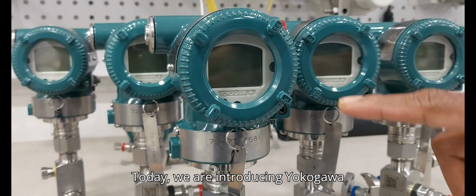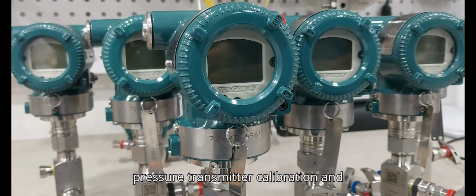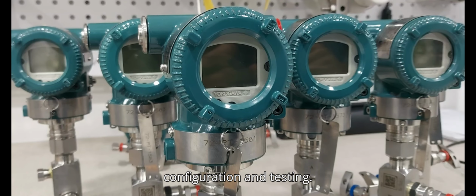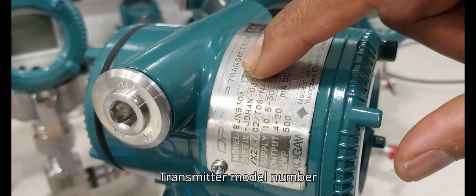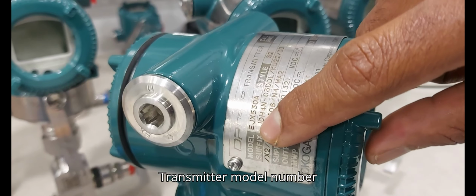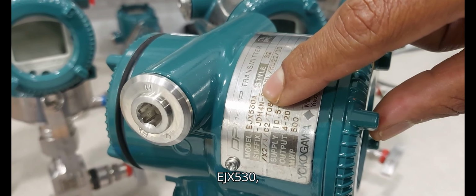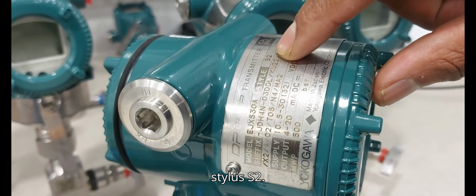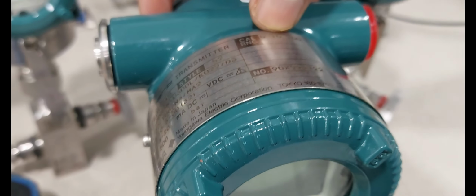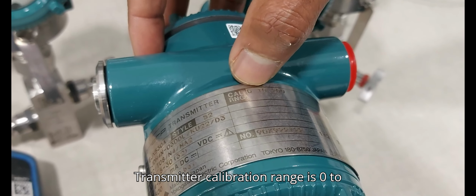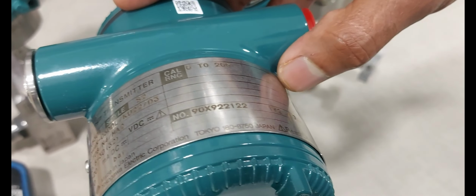Today we are introducing Yokogawa pressure transmitter calibration, configuration and testing. Transmitter model number EJX530, style S2. Transmitter calibration range is 0 to 200 bar.